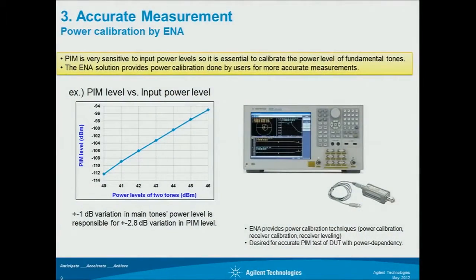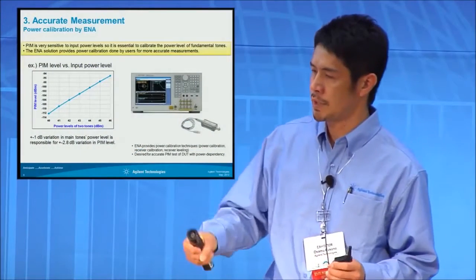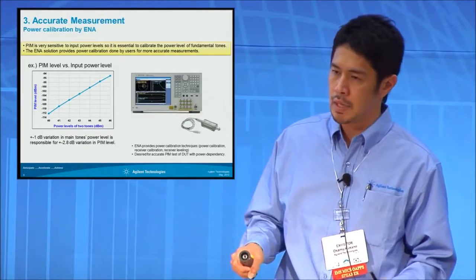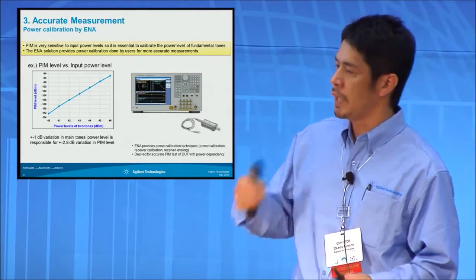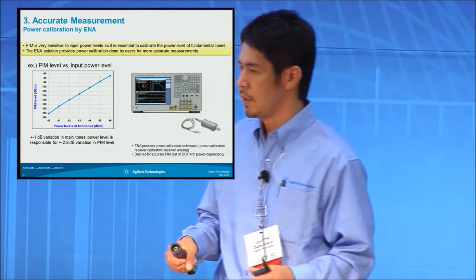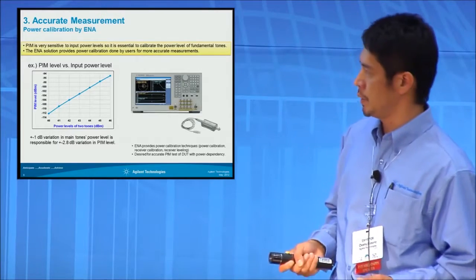More accurate measurement: because the network analyzer supports user calibration, and by using a power sensor, we can have user calibration of the whole configuration. So users can perform daily calibration of the system for better measurement accuracy.